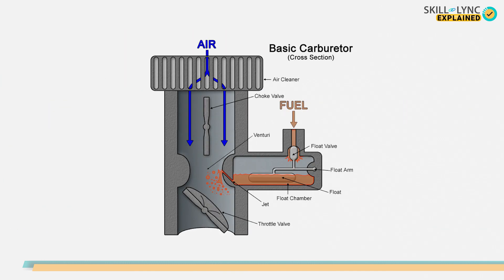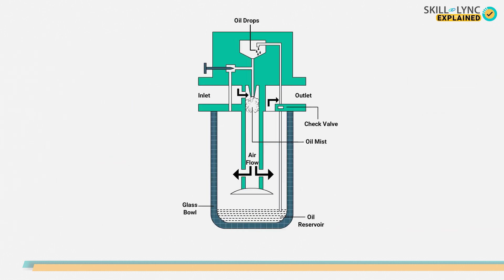The lubricator works on a principle similar to petrol-air mixing in a car's carburetor. As the air enters the lubricator, a venturi ring causes the velocity to increase. Due to this, a pressure reduction is observed, which causes the oil to be drawn up via a riser tube.